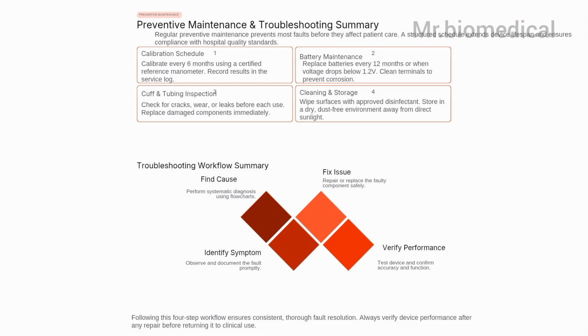So, before we finish, I have one final question. Which is better, repairing a failed device or preventing failure in the first place? Of course, prevention is better than cure. That's why preventive maintenance is essential. As a service engineer, we should calibrate every 6 months, check the cuffs and tubing regularly, replace weak batteries, clean the terminals, and store devices properly. Whenever a fault occurs, follow the 4 steps: identify the symptom, find the root cause, fix the problem, and verify the performance. Okay? Remember, we are not just repairing the equipment, we are ensuring accurate diagnosis, patient safety, and quality healthcare.